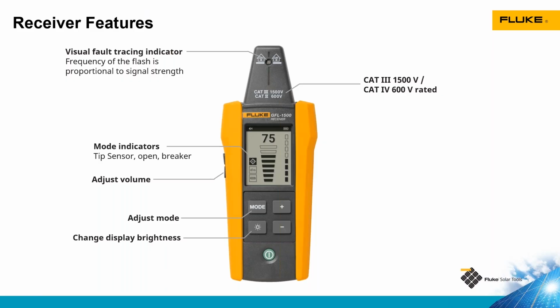This is also category 3 1500 volt, category 4 600 volt rated. We can adjust the sensitivity of the receiver, and we can see the signal strength both in the bar graph and in the number at the top of the display. And we can adjust the sensitivity with the up and down, the positive and negative buttons on the receiver.